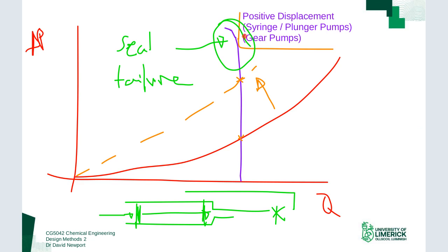So I've covered quite a lot of material here. The key point is that you always work off the pressure-flow curve — that's what you always want to produce for your system. Match your pump to the system: size your pump, match it to the system, understand how your pump behaves in the context of your system, and base all your design decisions on this curve.